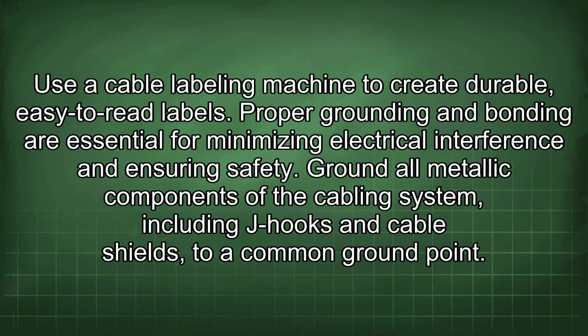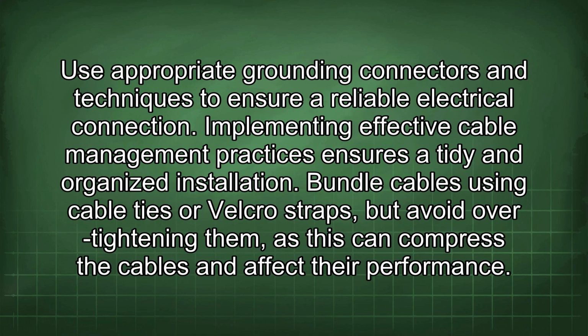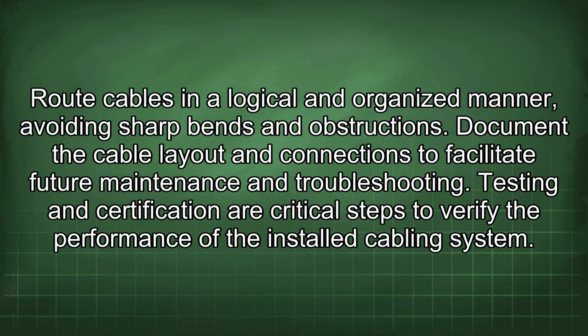Proper grounding and bonding are essential for minimizing electrical interference and ensuring safety. Ground all metallic components of the cabling system, including J-hooks and cable shields, to a common ground point. Use appropriate grounding connectors and techniques to ensure a reliable electrical connection. Implementing effective cable management practices ensures a tidy and organized installation. Bundle cables using cable ties or Velcro straps, but avoid over-tightening them, as this can compress the cables and affect their performance. Route cables in a logical and organized manner, avoiding sharp bends and obstructions. Document the cable layout and connections to facilitate future maintenance and troubleshooting.